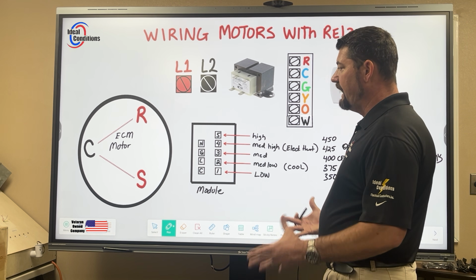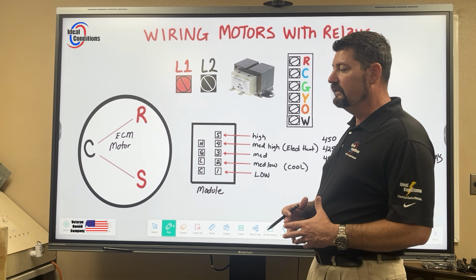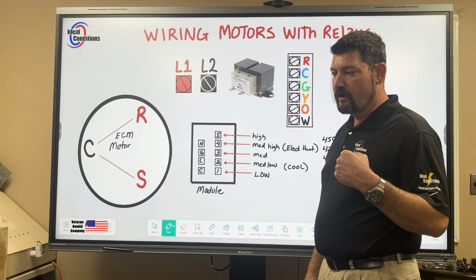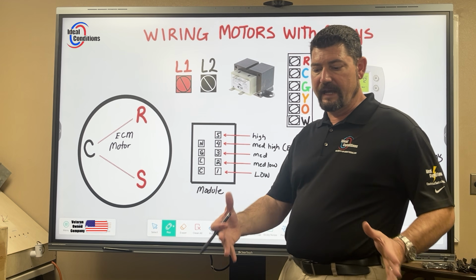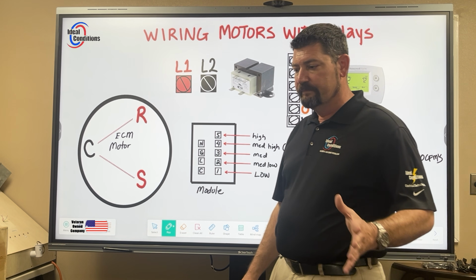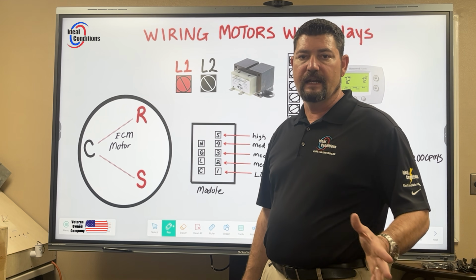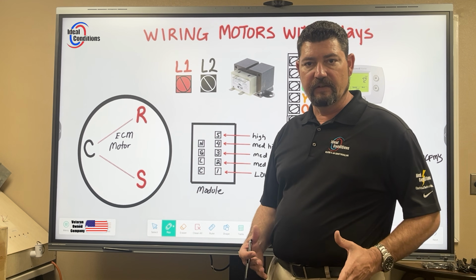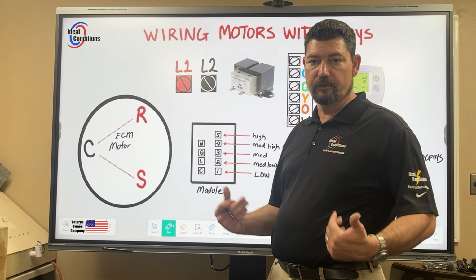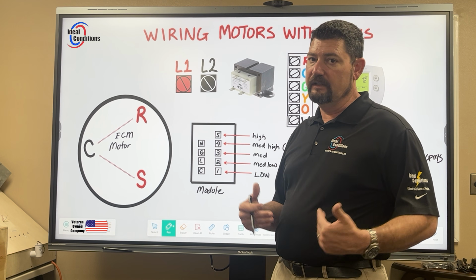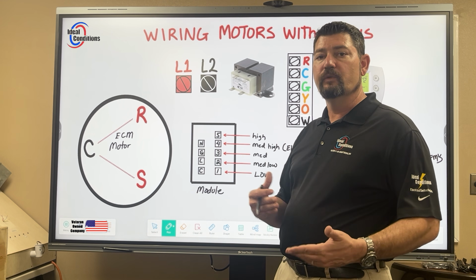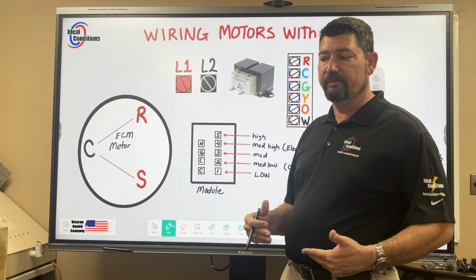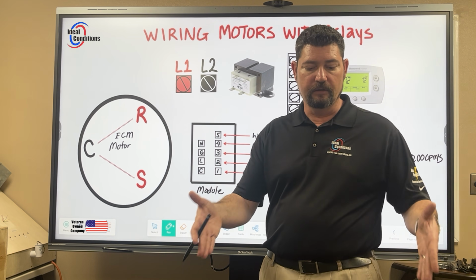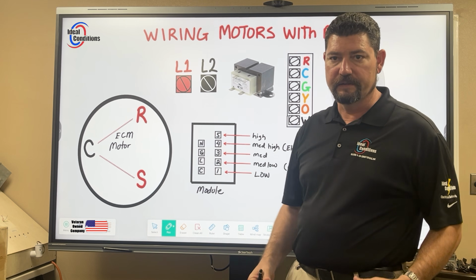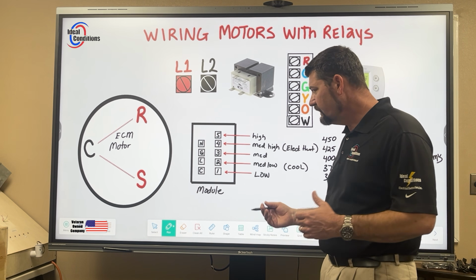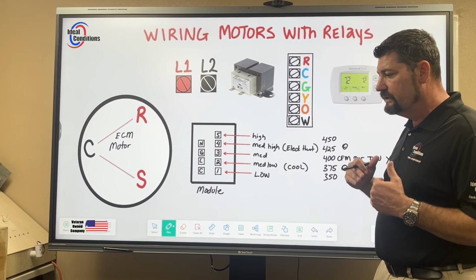Other things that are a factor on these ECMs and what causes these ECMs to go bad are high static pressure. So when we had it in our perspective in the lab, we had no static pressure on it because it was outside of a cabinet. And if you're testing this, your blower door is typically off. And if you're testing it, you're not going to be at the amp draws that you would normally be running at, or even be able to test static pressure because your panel is off, just like I couldn't with it sitting here on the table with just 230 volts on it. And so it's always good to test static pressure.